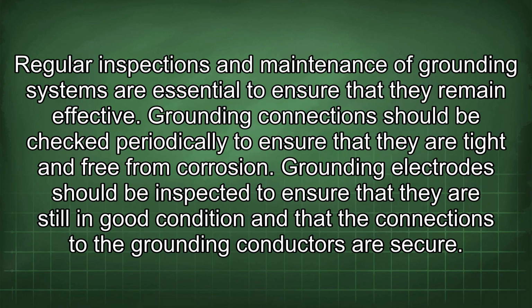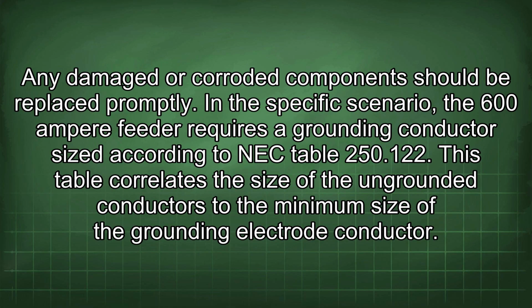Regular inspections and maintenance of grounding systems are essential to ensure that they remain effective. Grounding connections should be checked periodically to ensure that they are tight and free from corrosion. Grounding electrodes should be inspected to ensure that they are still in good condition and that the connections to the grounding conductors are secure. Any damaged or corroded component should be replaced promptly.